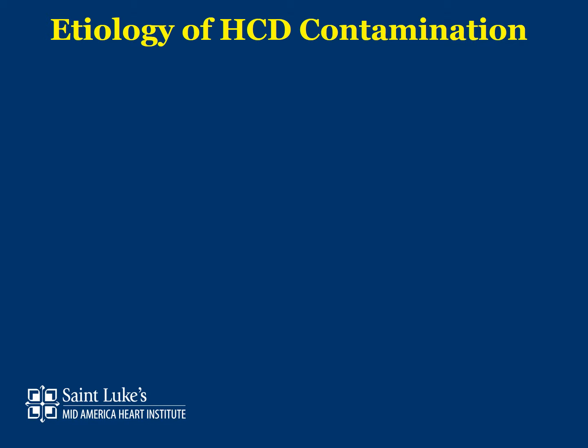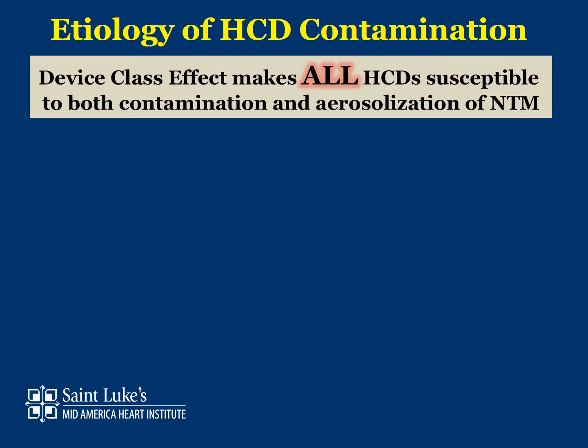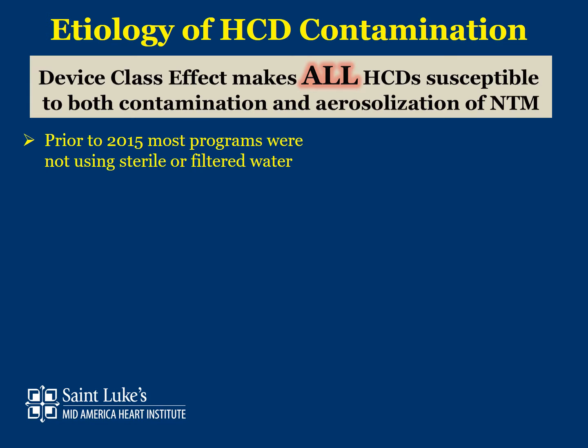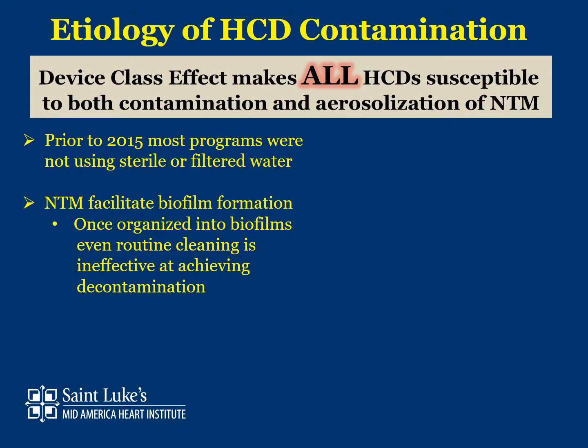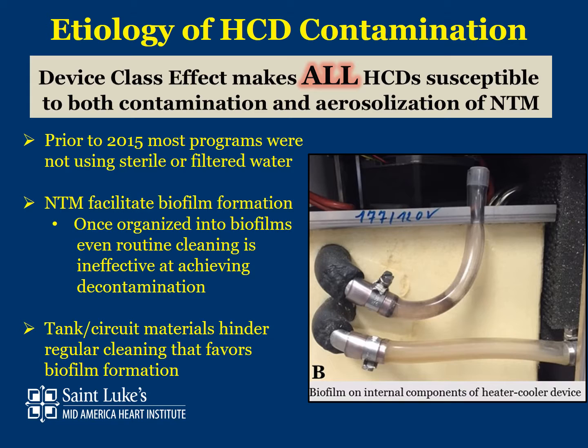When we look at the etiology of heater-cooler device contamination, it's not just one manufacturer, but there appears to be a device class effect that makes all heater-cooler devices susceptible to both contamination and aerosolization of NTM. Prior to 2015, as I noted, most programs were not using sterile or filtered water. Once a device becomes contaminated, NTM are prolific biofilm formers. Once organized into biofilms, even routine cleaning is ineffective at achieving decontamination. And finally, tank and circuit materials can hinder regular cleaning that favors biofilm formation. When I came back from the FDA meeting, I took the panels off our 8 devices, and 2 of our devices looked like this. They were obviously taken out of service.